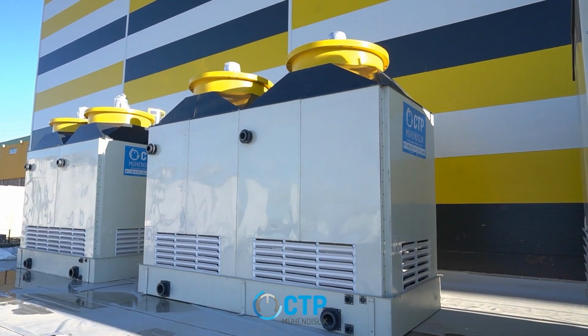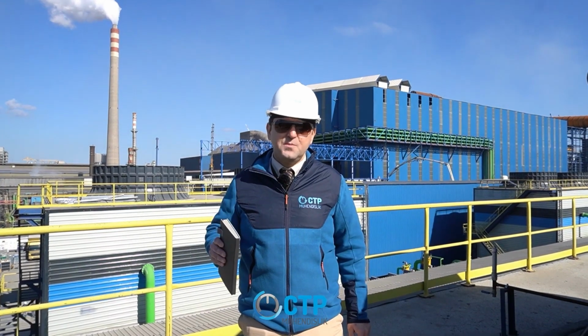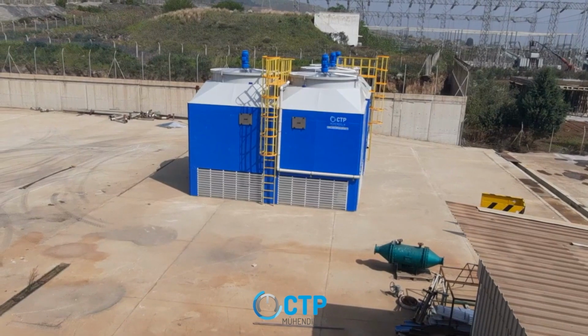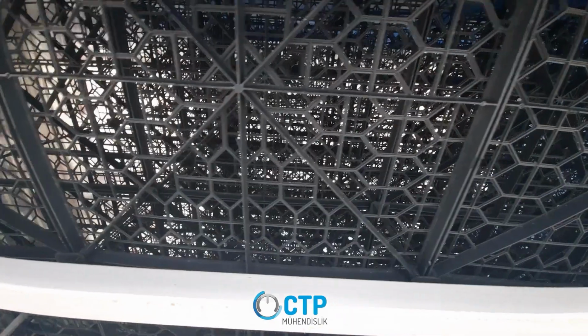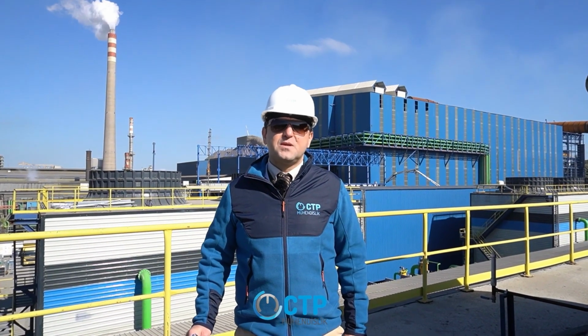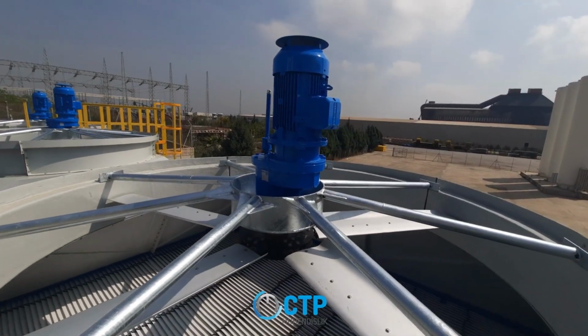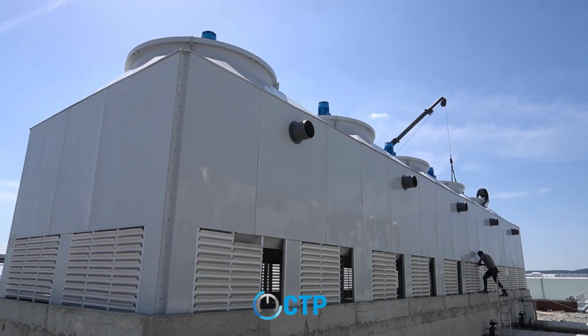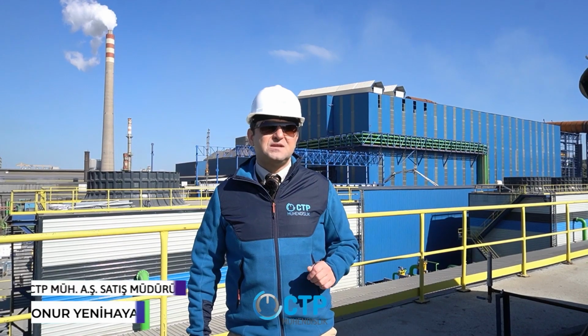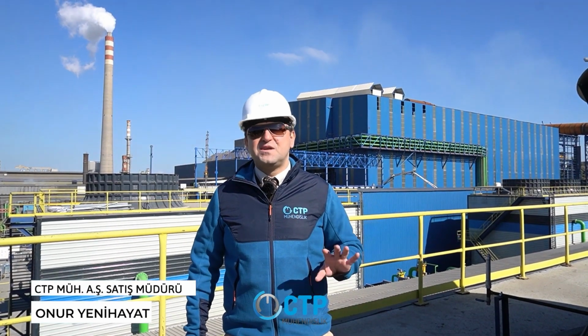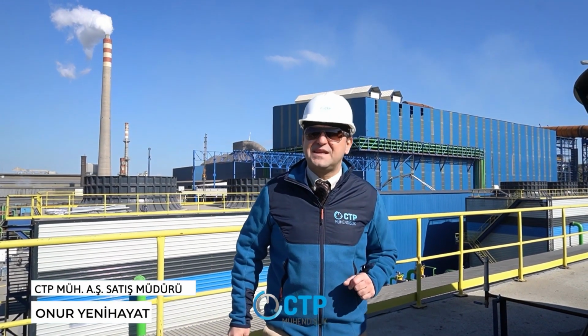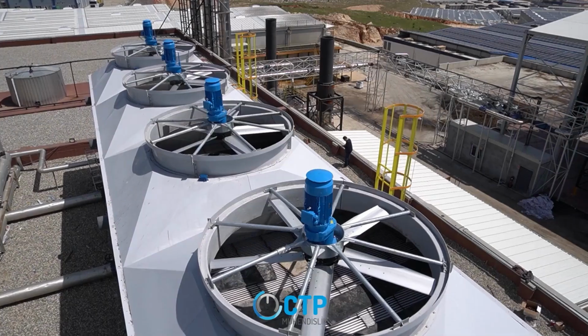85 to 90% of the performance you get from a cooling tower comes from evaporation. When water changes from liquid to gas, that is, when it turns into vapor, it absorbs 540 kilocalories of heat, even if its temperature doesn't change at all. The heat that water absorbs as it changes from a liquid to a gas provides the vast majority of the cooling performance, somewhere between 85 to 90%. In other words, heat transfer by conduction only contributes about 10% and at most 15% to the overall cooling of the water. The main cooling actually occurs through evaporation.